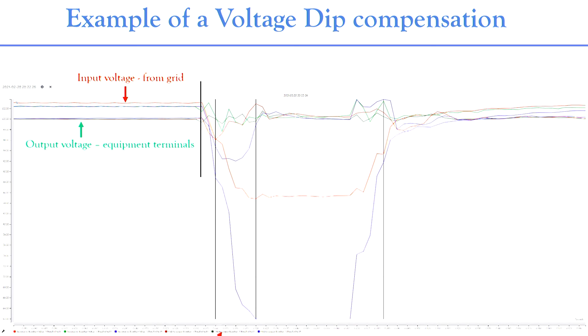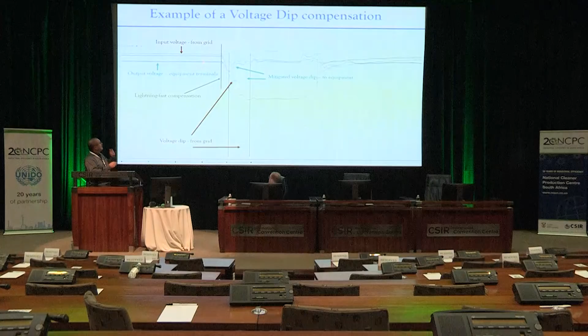I've measured the input voltage coming from the grid and the output voltage going to the plant, and you can see it looks much better. During the dip condition, it was boosted back - this is a real measurement of what happened. Don't worry too much about the detail, the resolution isn't great, but the point is it happened instantaneously, near instantaneously. You can't even see the delay. That's how fast power electronics can do this now.